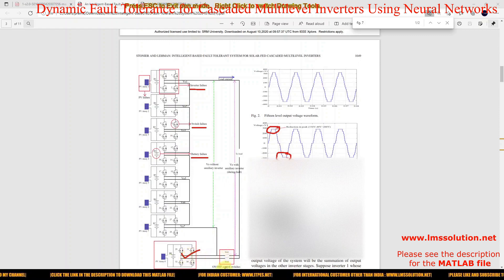During normal operation, we are using two switches. SA1 equals 1 and SA2 equals 0, meaning the auxiliary inverter is not connected to the system during normal operation. When a fault occurs, SA1 equals 0 and SA2 equals 1, so the auxiliary inverter is included in the system. We also need to provide switching logic based upon where the fault has occurred.